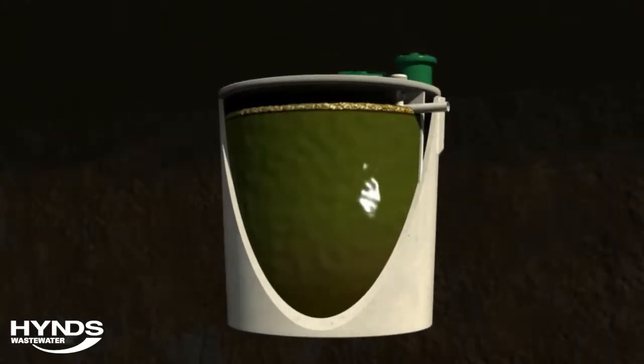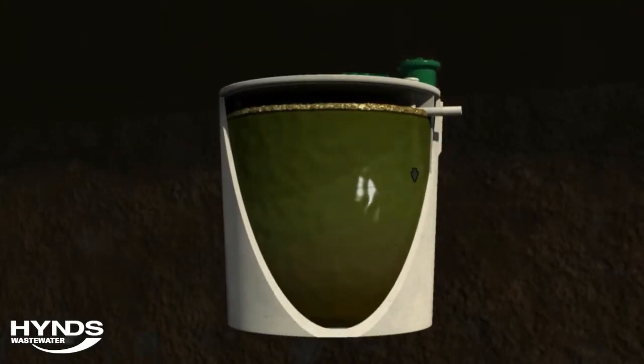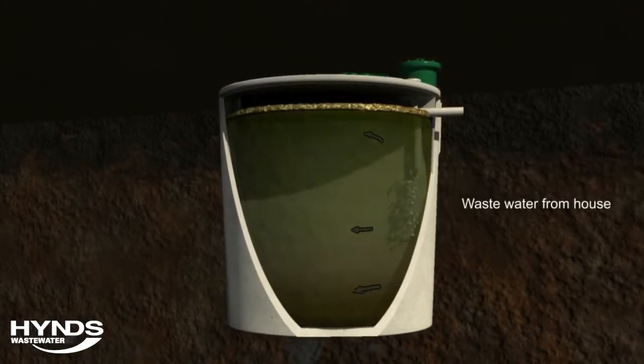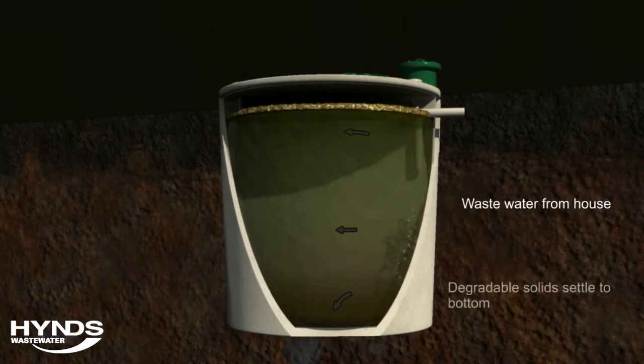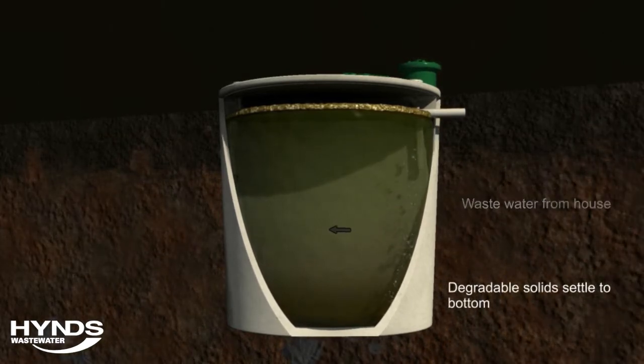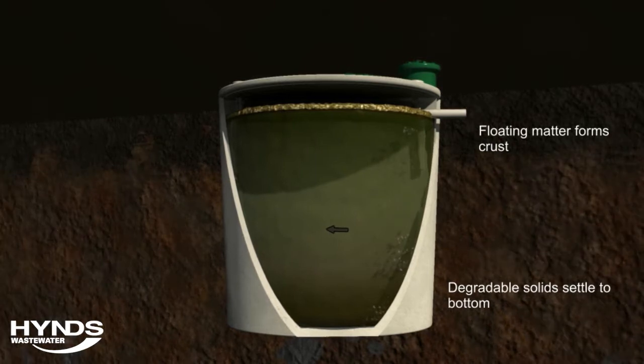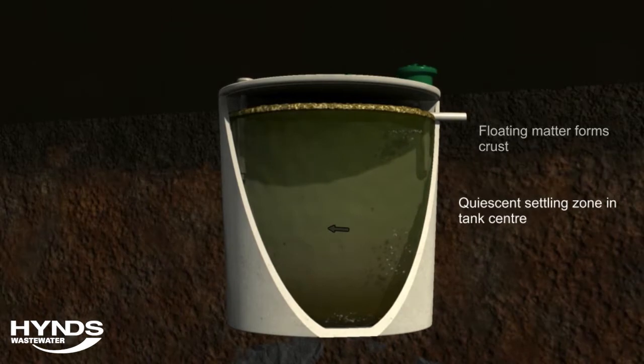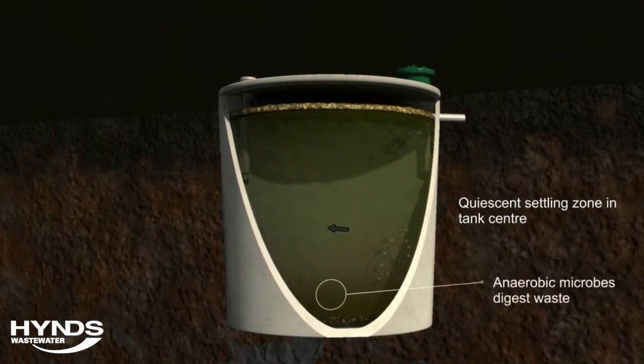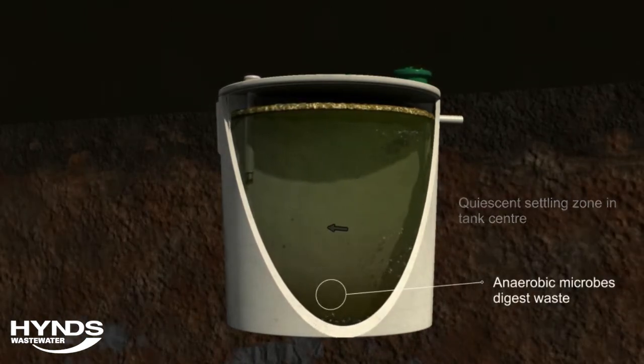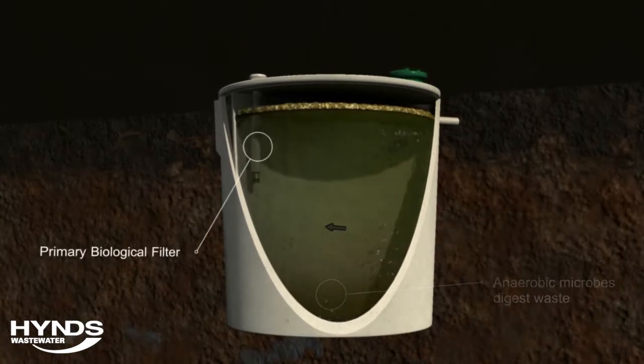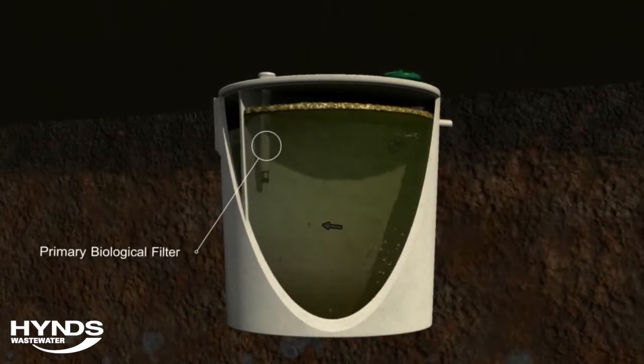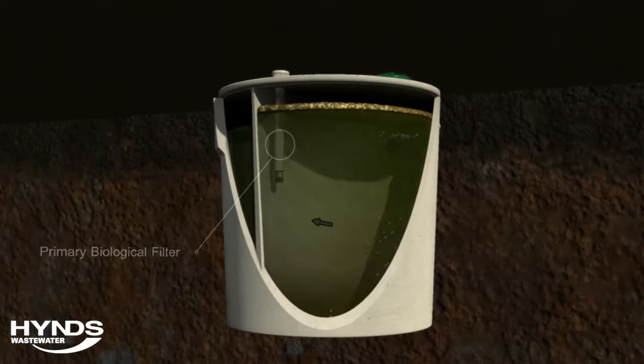The household wastewater enters the treatment system into a primary treatment chamber. As the wastewater passes through the primary chamber, solid matter sinks into the bottom of the tank and begins to decompose. Floatable material rises to the top of the chamber and forms a solid crust that floats on top of the wastewater. This crust is vital in containing any gases formed in the anaerobic process taking place in the tank. The wastewater passes through a biological filter on the outlet of the primary chamber.